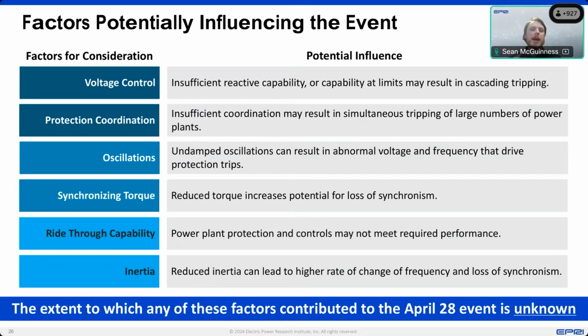then that can create a common mode failure because the overvoltage protection is not coordinated. So you have an overvoltage and all the units that see that will all trip at pretty much the same time because they're all trying to meet your grid code or interconnection requirement. So in some grids, or as we've seen elsewhere in the world, you have situations where a prolonged undervoltage or a prolonged overvoltage condition can result in the disconnection of more power plants than your standard loss of largest infeed assumption. So if you assume that maybe 2 or 3 gigawatts is your largest infeed, you can have that or more disconnecting for a sustained abnormal voltage event.